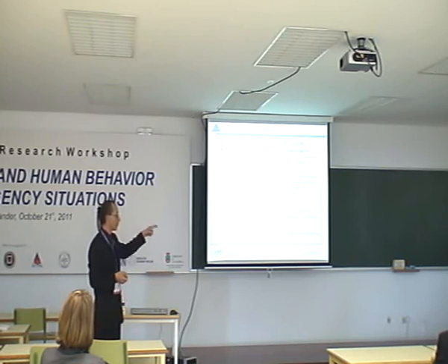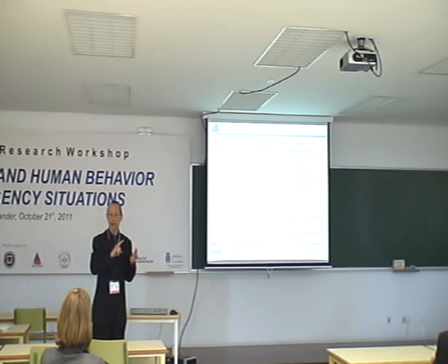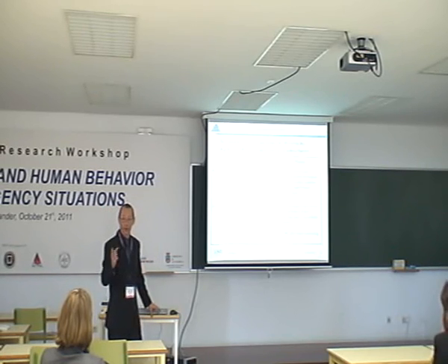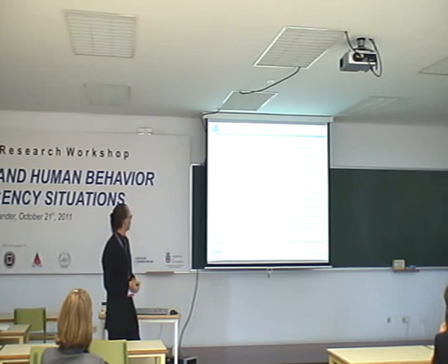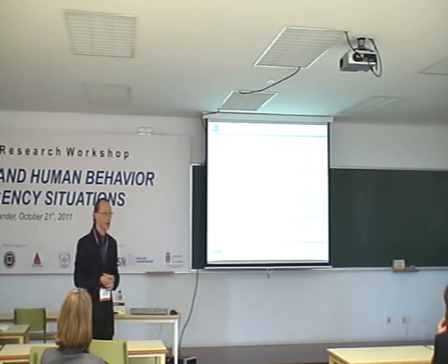And for this part, building the source term, because you have to feed the matrices, you have to make some experiments on materials to know what they will emit as species under well-ventilated condition, high flux condition, and so on. So this may be time-consuming, but you can build a database along the time.